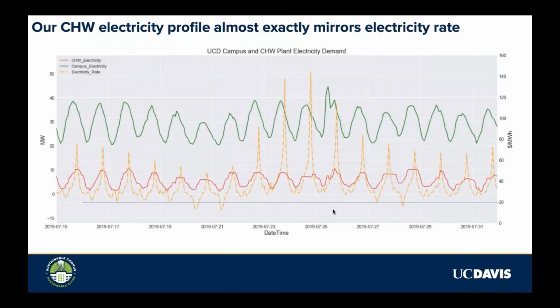And so this graph shows our total campus electricity, and in green, our chilled water system electricity usage in red, and then the electricity rate in dashed orange. And what you can see is that our peak chilled water electricity demand coincides with the peak rate. And so this means there's a lot of opportunity for optimizing the load profile.